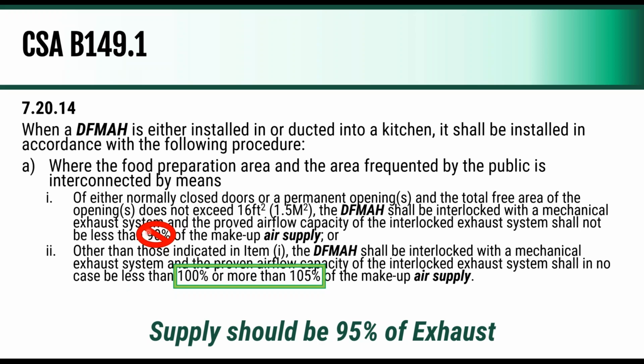Obviously, this part here says it should be no less than 90% of makeup air. So theoretically, you could go to 120% of the supply on the exhaust, which would be 80%, depending on how you look at it. And that would be a negative. That's something we do see, but we don't always know the size of openings in the kitchens. So we typically default everything to 95% of exhaust when you're doing a direct fired makeup air unit. Direct fired makeup air units are the most common ones that we see. However, we are seeing more and more that are indirect.